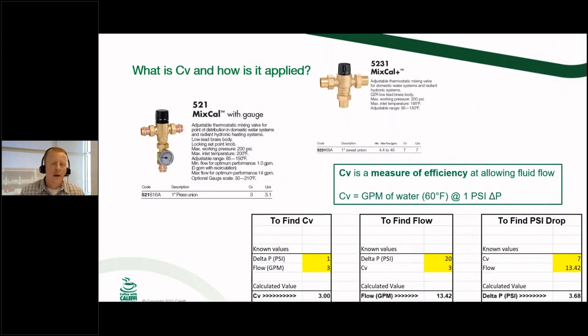All right, now another one that we want to talk about here is CV. You'll probably notice this on pretty much every valve in the market, whether it be a mixing valve, a balancing valve, a zone valve, a ball valve. You're probably going to find a CV value. But what is CV? What do you do with it? How do I use CV? Okay, CV, and I'm just going to read it right off here because I think it's the perfect way of describing it. It is a measure of efficiency at allowing fluid flow.